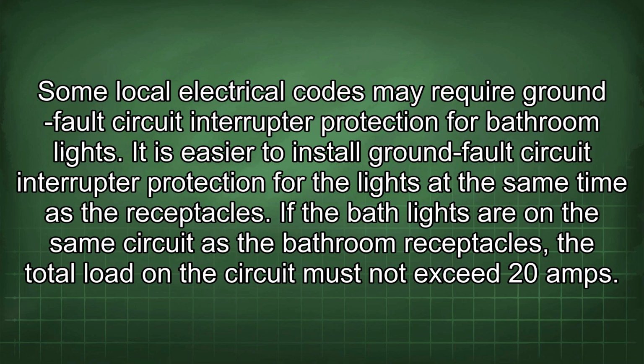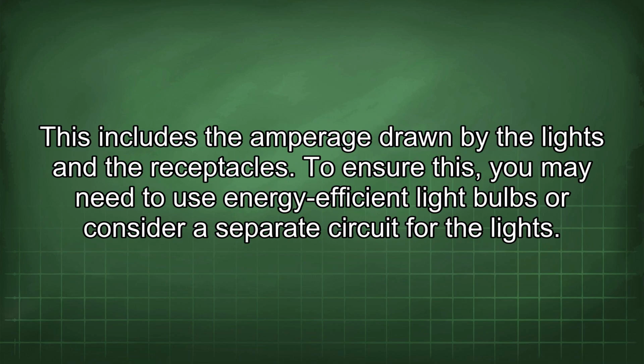If the bath lights are on the same circuit as the bathroom receptacles, the total load in the circuit must not exceed 20 amps. This includes the amperage drawn by the lights and the receptacles. To ensure this, you may need to use energy-efficient light bulbs or consider a separate circuit for the lights.